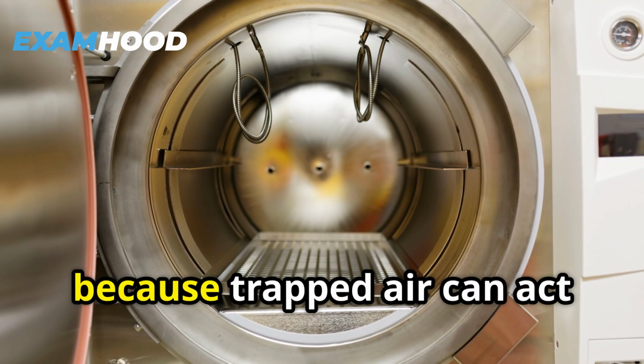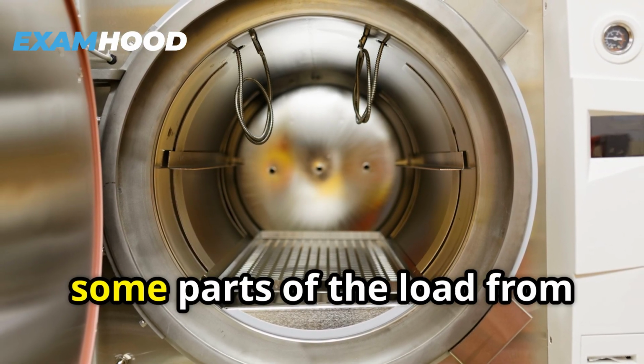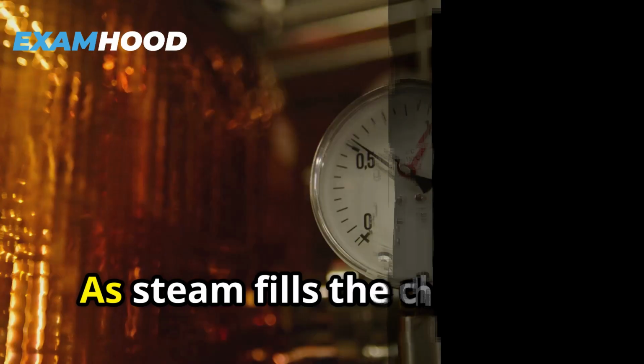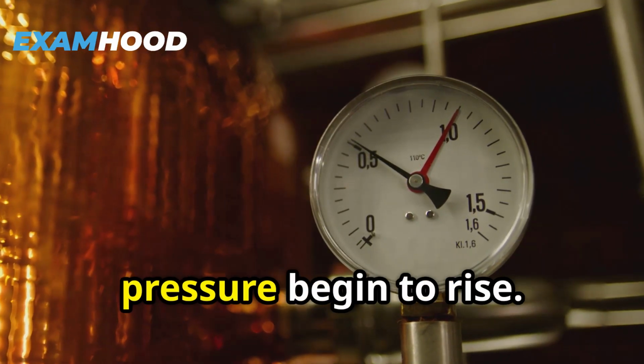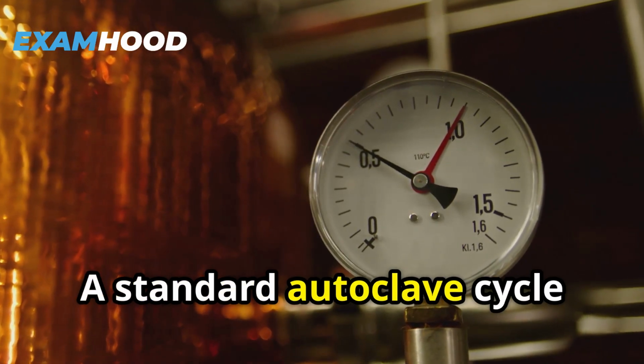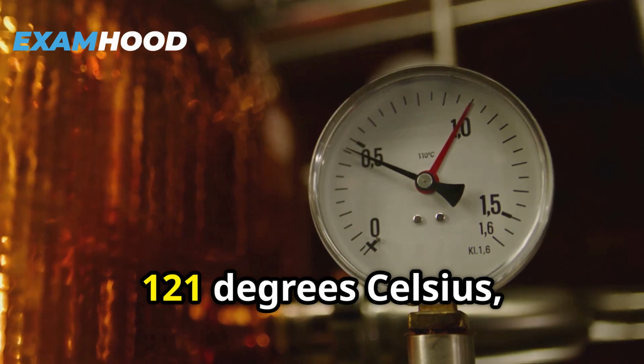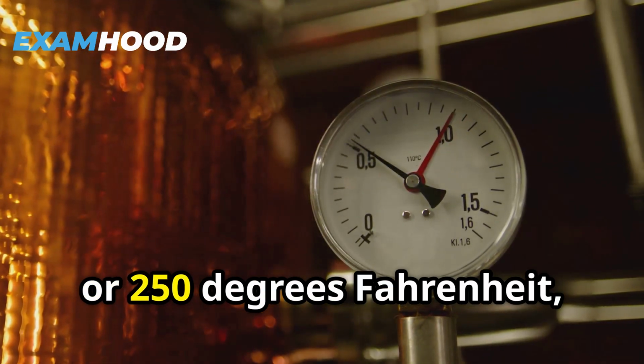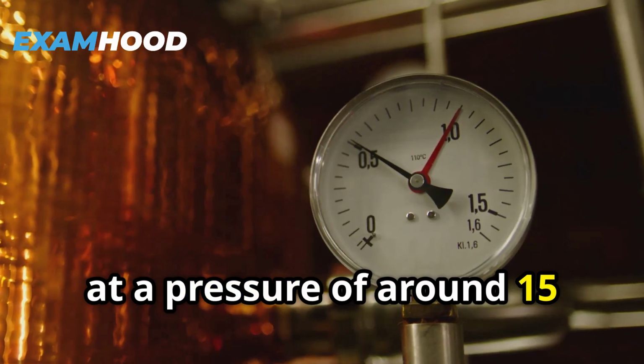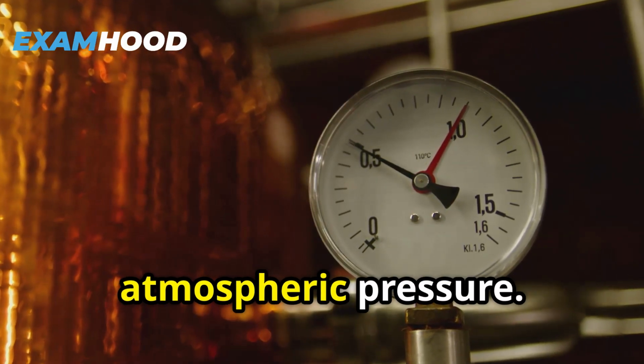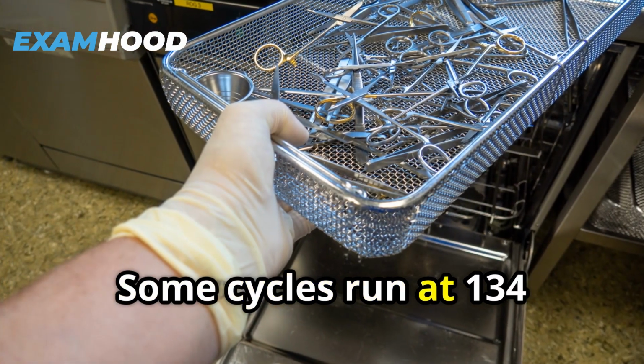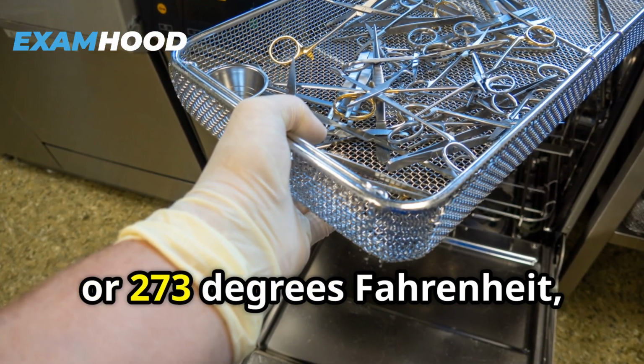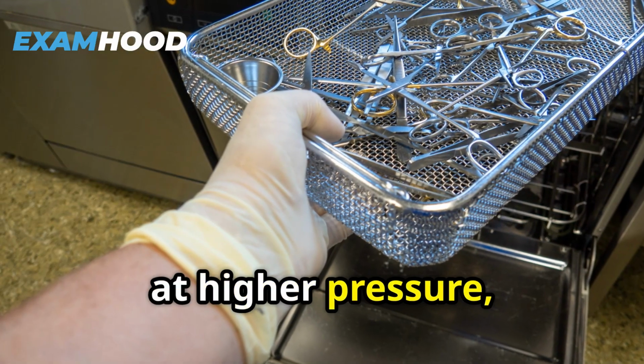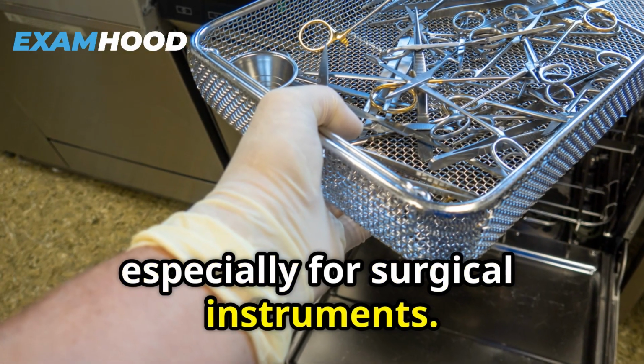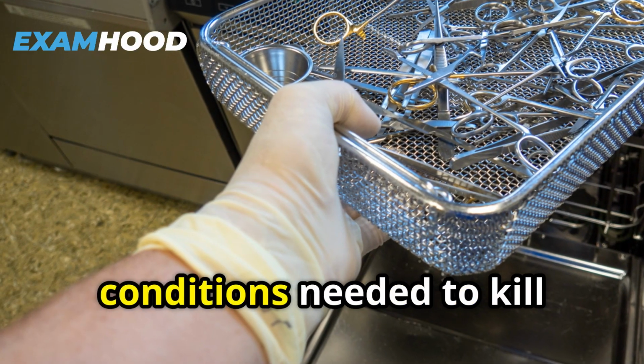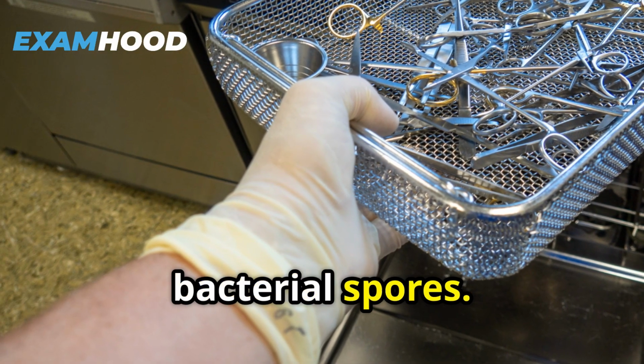Removing air is essential because trapped air can act as an insulator and stop some parts of the load from reaching the correct temperature. As steam fills the chamber, both temperature and pressure begin to rise. A standard autoclave cycle uses a temperature of about 121 degrees Celsius or 250 degrees Fahrenheit at a pressure of around 15 pounds per square inch above atmospheric pressure. Some cycles run at 134 degrees Celsius or 273 degrees Fahrenheit at higher pressure, especially for surgical instruments. At these settings, the autoclave reaches the conditions needed to kill even heat-resistant bacterial spores.